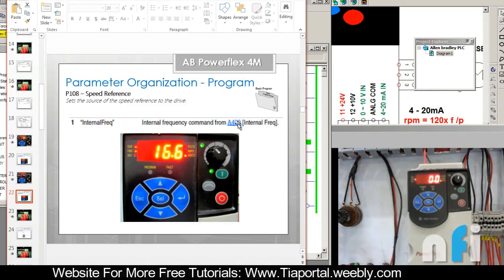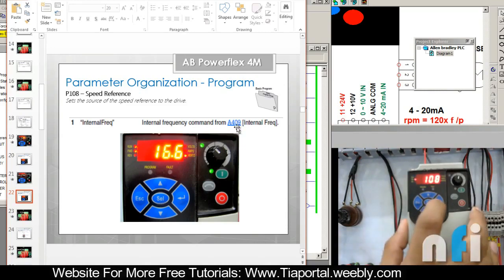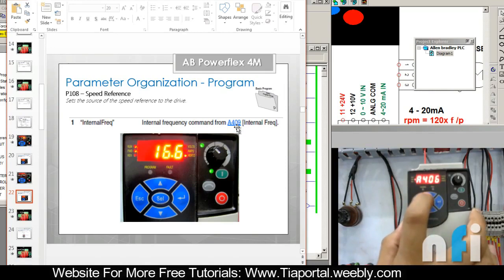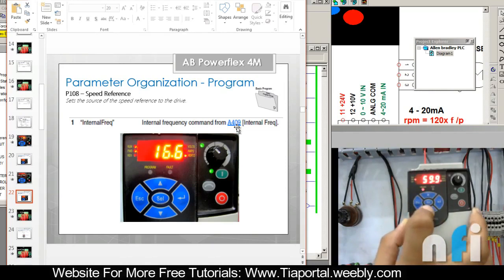The internal frequency is defined by A409. Let's go to A409. To navigate there — this is B, you can change that to A. A is for advanced parameters. Let's go to 9. This is by default 60, so let me change that to 15 Hertz. It's up to you how much fixed frequency you want. In my example, I'm just taking 15 Hertz.